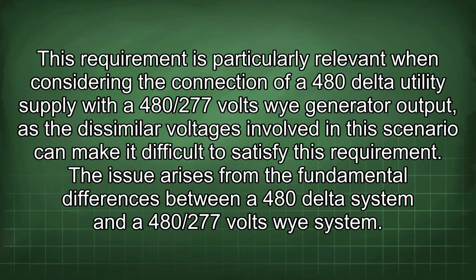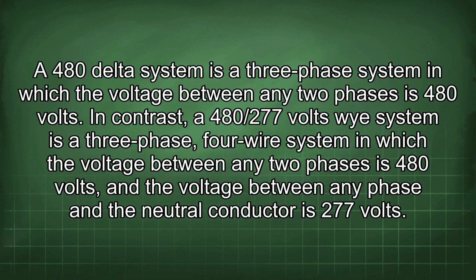requirement. The issue arises from the fundamental differences between a 480 delta system and a 480/277 volts Y system. A 480 delta system is a three-phase system in which the voltage between any two phases is 480 volts. In contrast, a 480/277 volts Y system is a three-phase, four-wire system in which the voltage between any two phases is 480 volts, and the voltage between any phase and the neutral conductor is 277 volts.